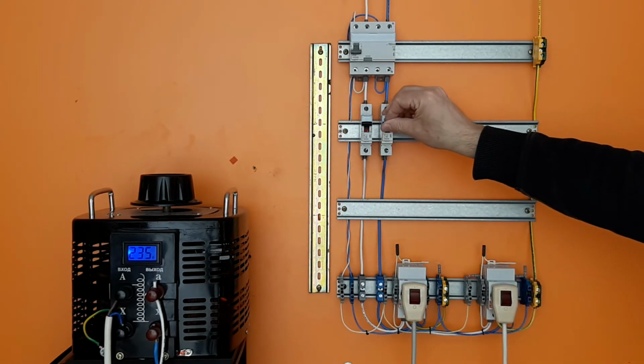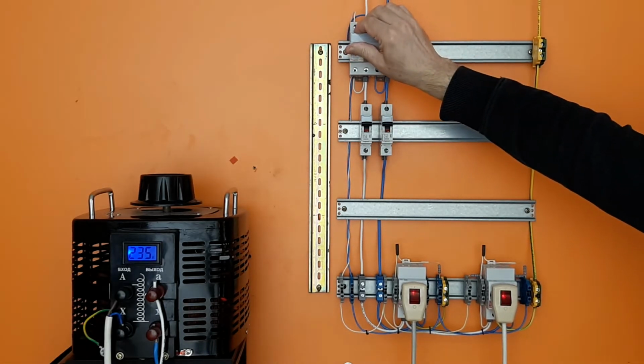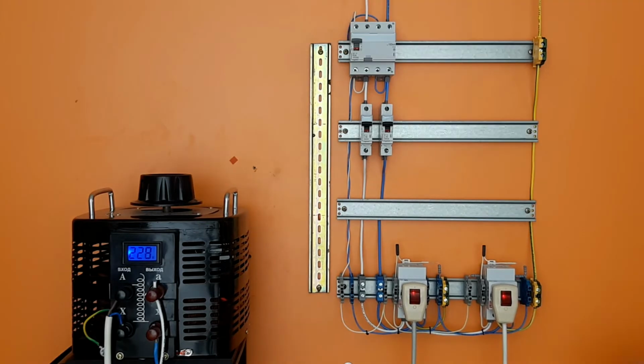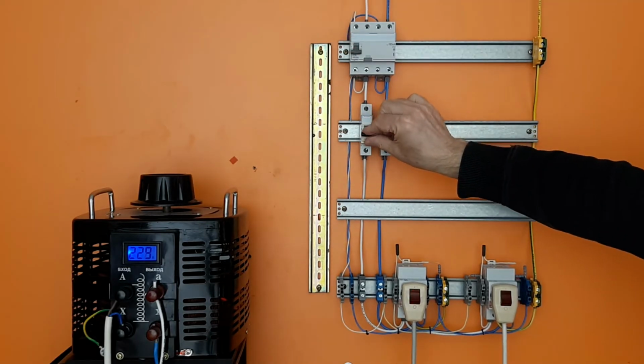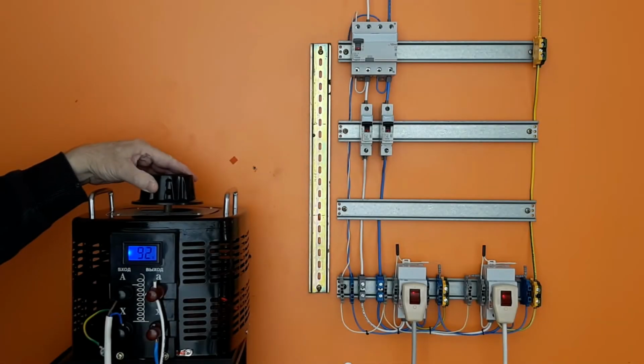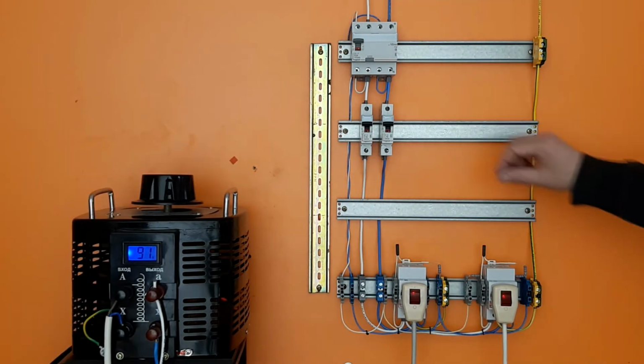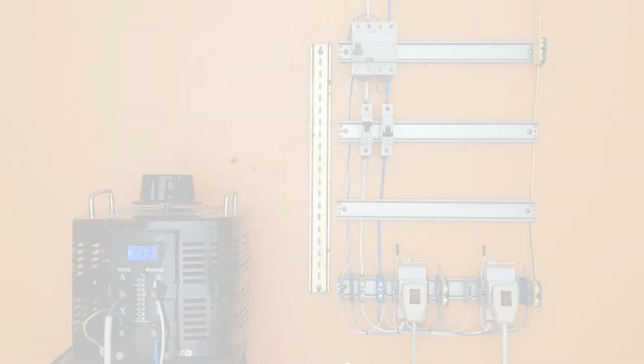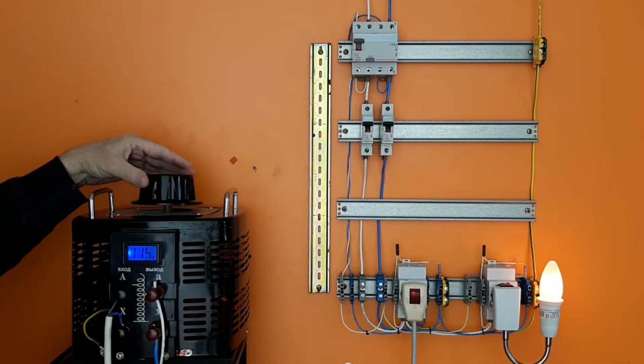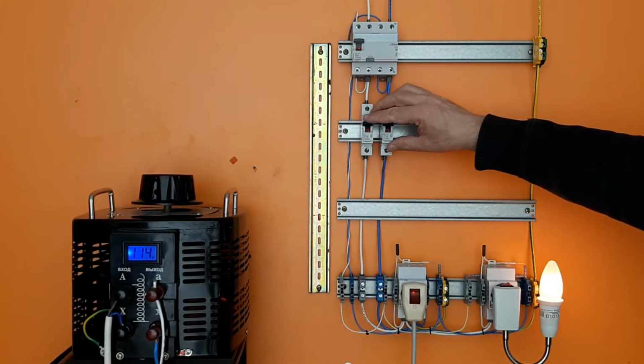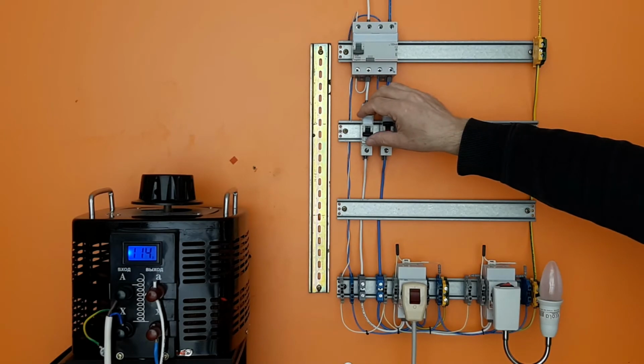Repeat the experiment. Now we break the phase conductor. It also provides the full protection from breakage. Next, we check the performance at low voltage. We obtain that for a load of 800 watts, the sensitivity to breakage is maintained at a voltage of 90 volts. For a 40-watt load, the minimum voltage was 115 volts.